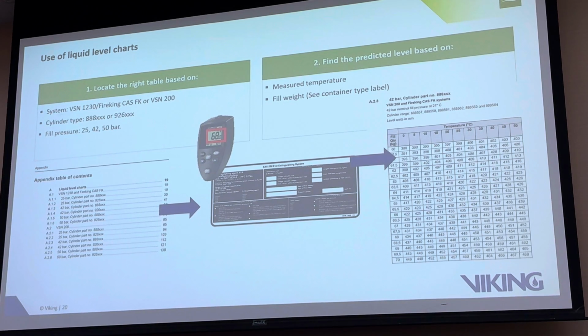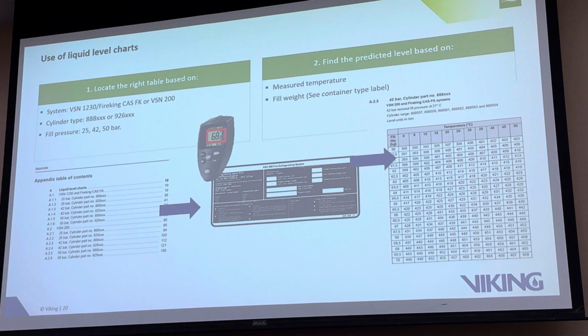So you measure the temperature, you identify your system, if it's a VSN 1230 or a VSN 200, you identify your cylinder type, you have your part number on the container label, you can see if it's an 888 or a 926. You know your working pressure, 25, 42, or 50. That's a system pressure, we don't need to read it in the pressure gauge.